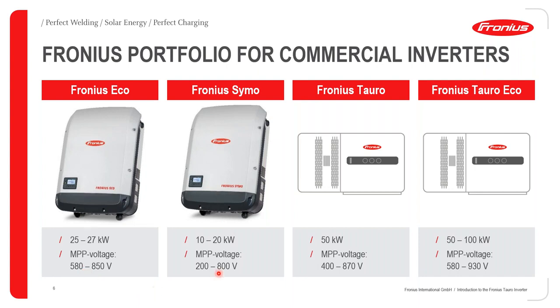Okay, so you can see that substantial difference between the two. The reason for this is that the Fronius Symo has a buck boost circuit integrated, so your MPPT voltage range is much larger. Then moving on to the Fronius Tauro, this will be the new 50 kilowatt commercial inverter. Your MPPT voltage range will be between 400 to 870 volts. Again, this inverter will have 3 trackers. Then having a look at the Fronius Tauro Eco. Okay, this inverter will either come in a power class of 50 kilowatts or 100 kilowatts, and its MPPT voltage range will be between 580 volts to 930 volts DC.